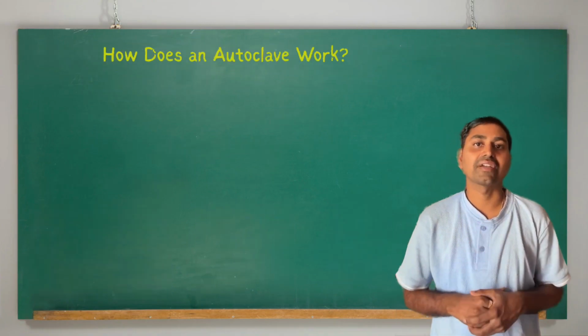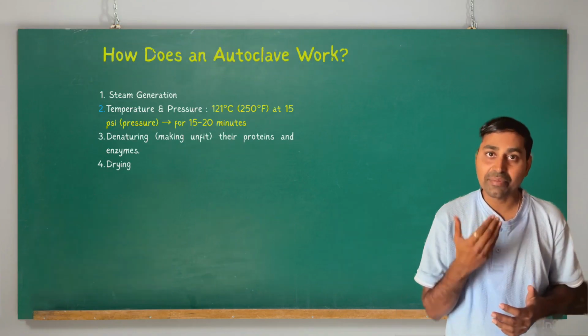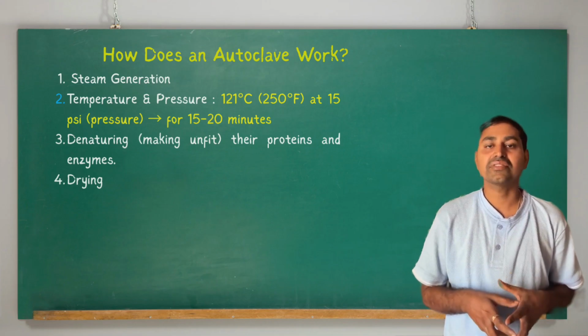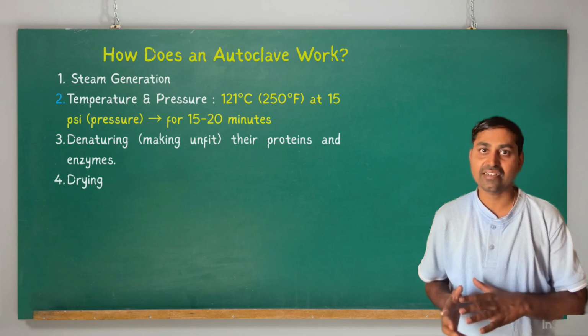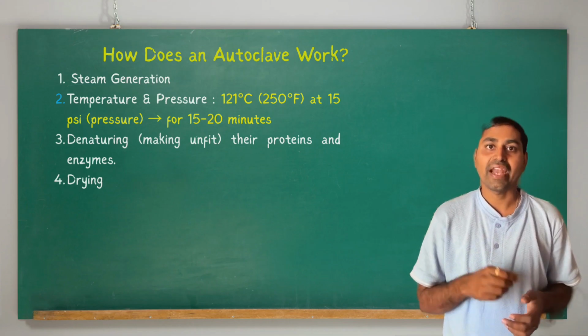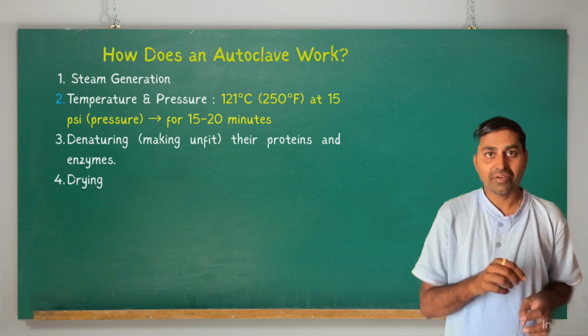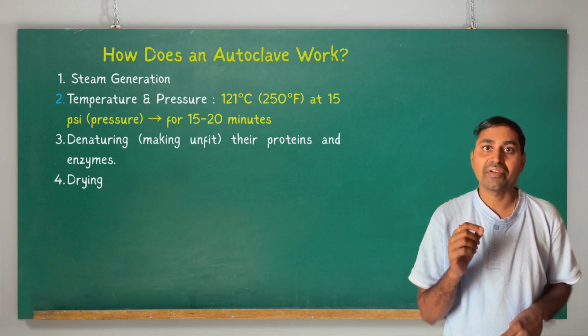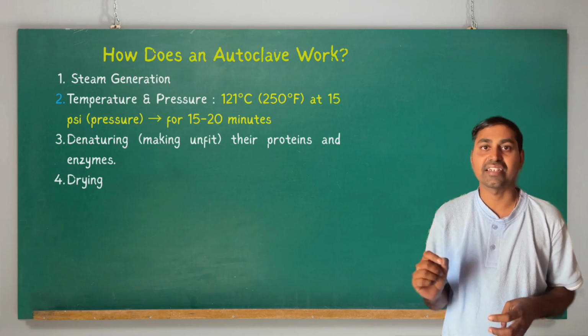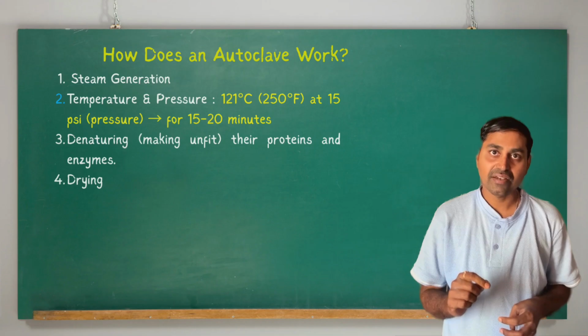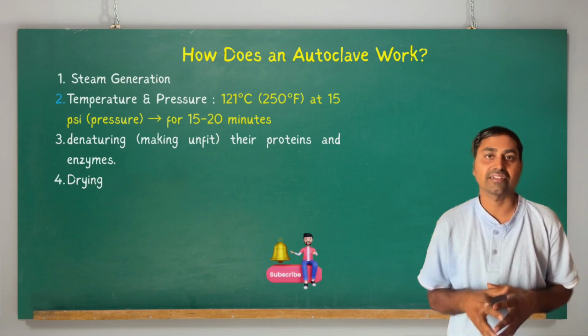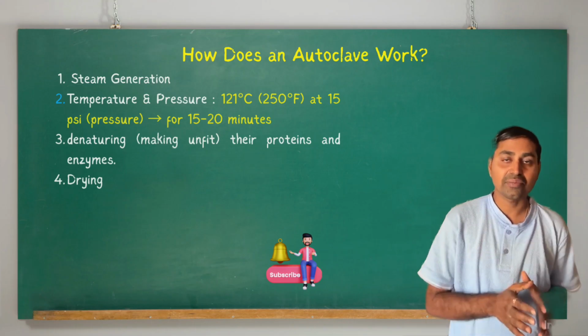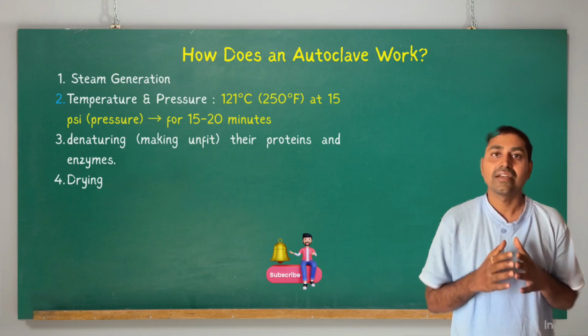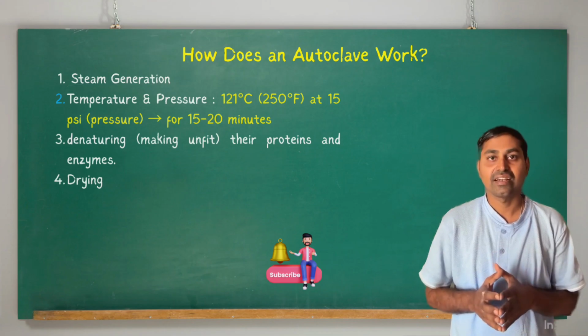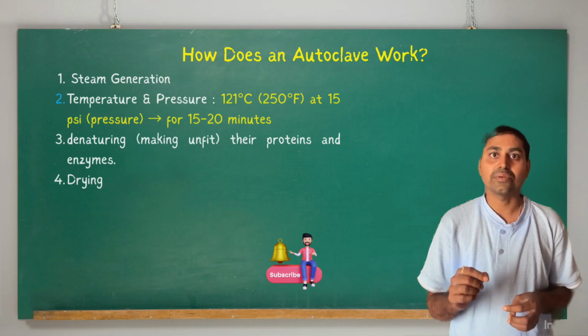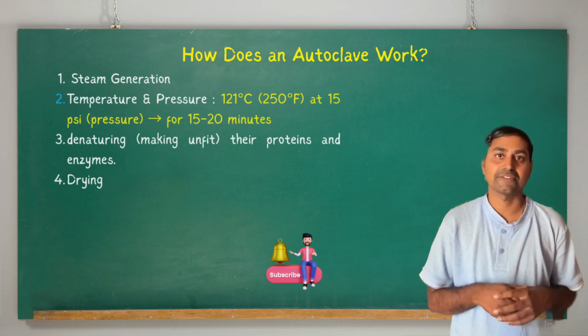Then how does an autoclave work? Autoclave works by steam generation, where water is heated to produce steam, and temperature and pressure are set at 121 degrees Celsius at 15 psi. Psi is the pressure. 121 degrees Celsius at 15 psi for about 15 to 20 minutes. This is the standard setting. In case of emergency, if we need any instruments very early, then we set temperature at 134 degrees Celsius at 30 psi for about 3 to 5 minutes. This is called flash sterilization.